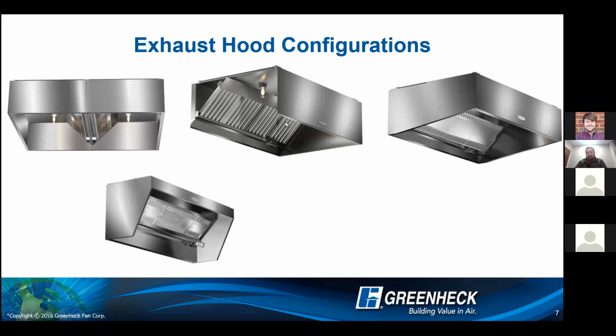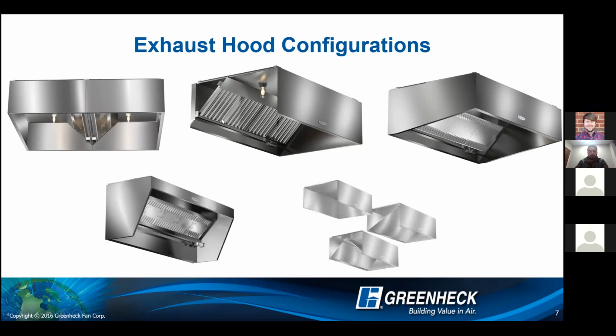The next is a low proximity hood, commonly referred to as a 5-guys hood. These hoods are hung about 36 inches above the appliances with an underhang requirement. Since they're so close to the appliances, they typically have a lower CFM requirement. A 5-guys hood is kind of slang for them. These are used in a lot of fast food applications where you have fryers and griddles. But as soon as you start having ovens or really hot charbroilers or something of that nature, the low proximity hood is no longer very effective.